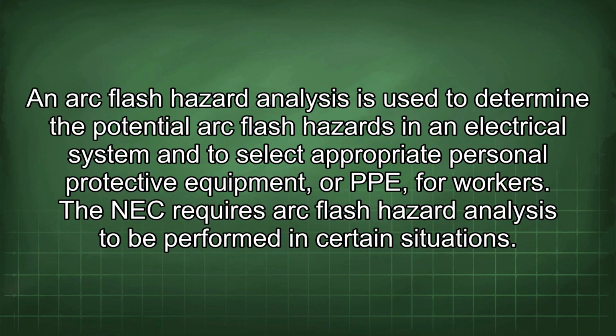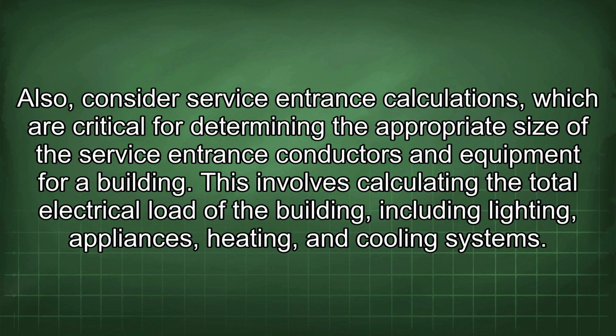An arc flash hazard analysis is used to determine the potential arc flash hazards in an electrical system and to select appropriate personal protective equipment, or PPE, for workers. The NEC requires arc flash hazard analysis to be performed in certain situations. Also, consider service entrance calculations, which are critical for determining the appropriate size of the service entrance conductors and equipment for a building. This involves calculating the total electrical load of the building, including lighting, appliances, heating, and cooling systems.